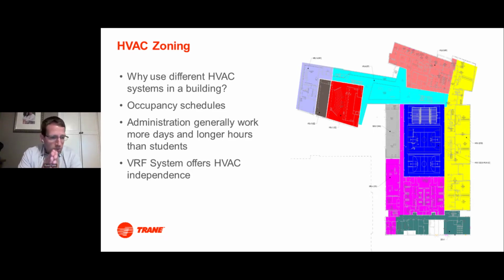And the reason why we do that is because admin staff in a school generally work longer during the day, and they don't have as many holidays and vacation days as the normal student population. We try to divorce this system from any central systems to allow the VRF system to operate without having to turn on your large chillers back at your mechanical rooms. That way it can operate almost independently of the rest of the building.